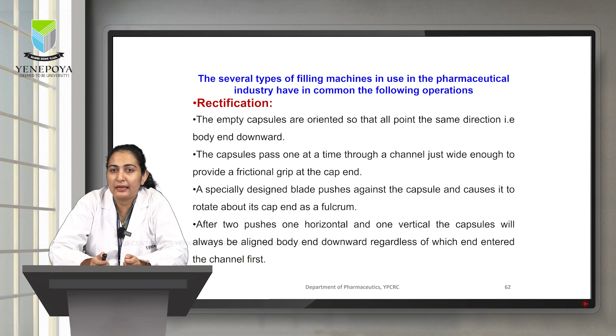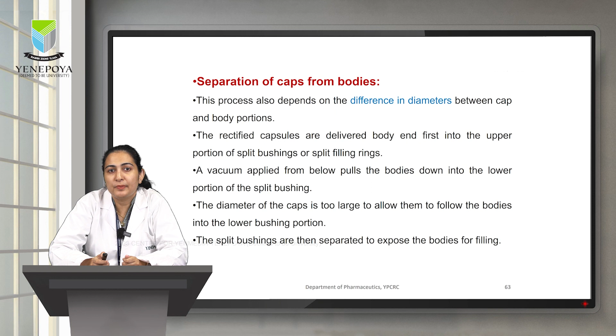The second principle, or second stage, in these filling equipments is separation of caps from the bodies. The separation of caps from the bodies is based upon the difference in diameter between the cap and the body portion. The rectified capsules are delivered body end first into the upper portion of split bushings or split filling rings. Next, a vacuum is applied from below, which pulls the body down into the lower portion of the split bushing. The diameter of the caps is too large to allow them to follow the bodies into the lower bushing portion. The split bushings are then separated to expose the bodies for filling of the material.